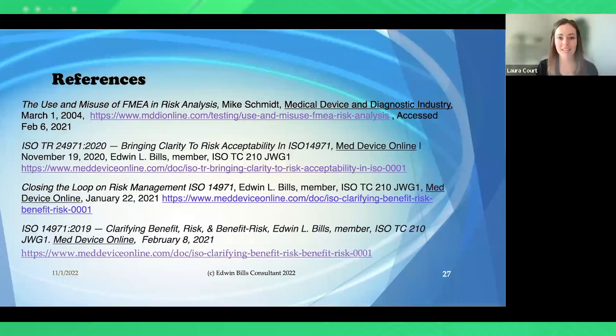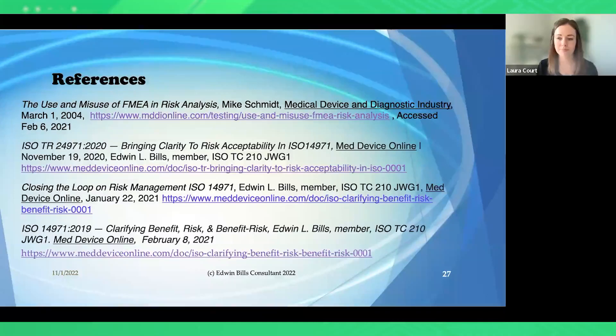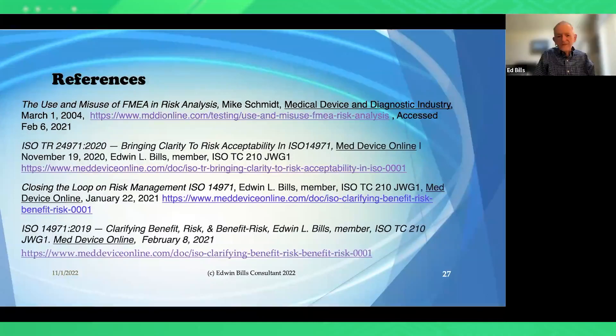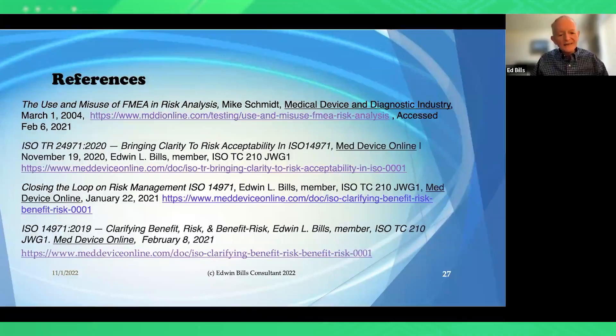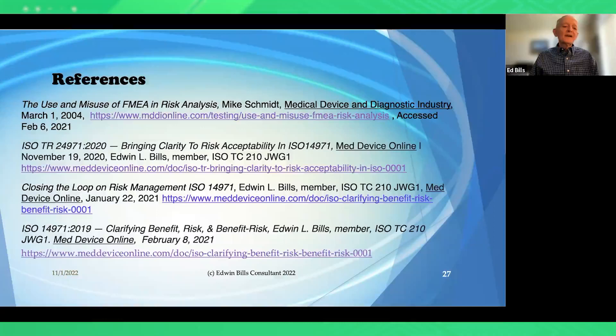A question came in: how do you feel about other standards repeating definitions from ISO 14971, for example IEC 62304? Is that good practice, or should they reference back to 14971? This is an ISO formatting requirement — that is simply the way things must be done under ISO. The problem arises when editions change: IEC 62304 references the 2007 edition, not the 2019 edition, so it refers to an older set of definitions. ISO does require that when a term is used from another standard, the standards must coordinate.